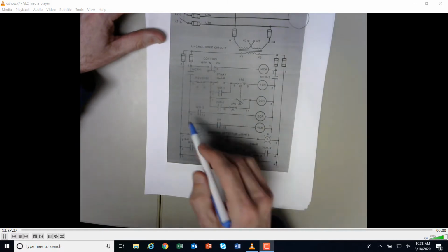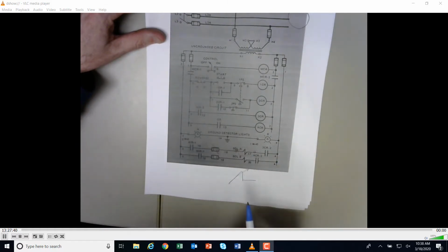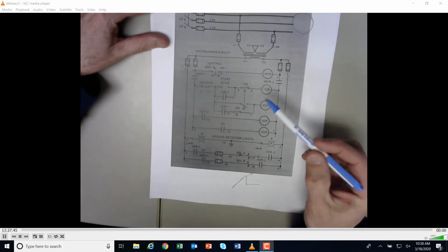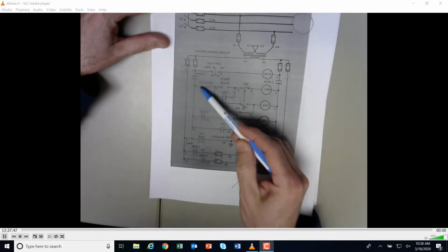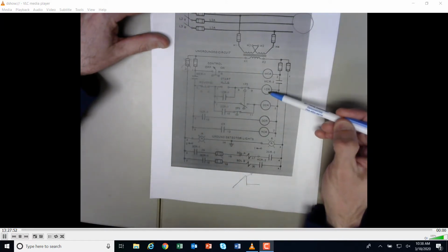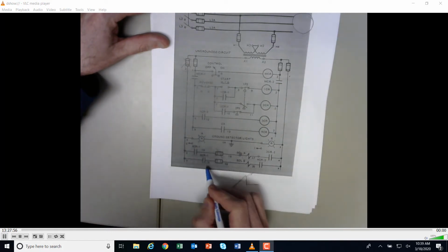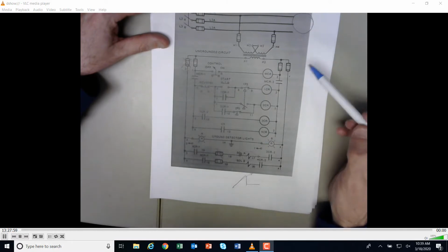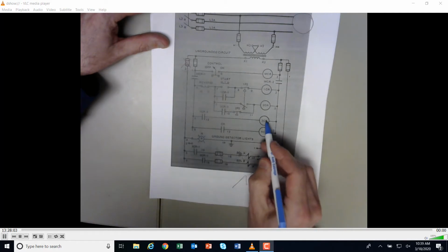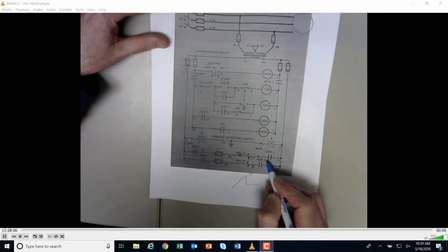These fuses here, for some reason, something went bad in this part of the process here, and let's say this fuse popped. Well, that's the same thing: the main control here is still working, because these control relays here control whether these rungs are true or not, we can still bring these rungs in.